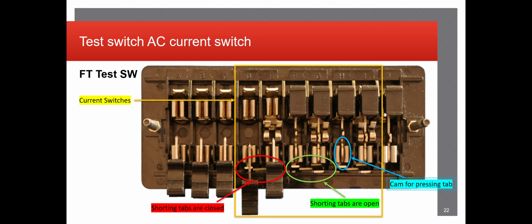The pressing tabs are for security reasons. You want to make sure that those are in all the way and make a good connection. Otherwise, there's going to be heat that you can probably feel if there's a poor connection, and maybe a little bit of buzzing depending on how poor the connection is. With AC power, if you're putting a relay into service and that happens, the relay is going to see funky current readings and probably operate whatever breaker it needs to, and could run into problems there.